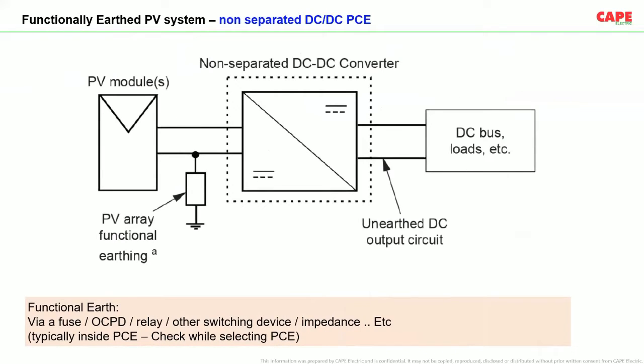This one is a non-separated DC system, but again functionally earthed. The purpose of the functional earthing is that whenever there is a fault in this particular circuit, the fault current will return back through this functionally earthed wire. And on that wire, there is a measurement mechanism and a disconnection mechanism, provided with the help of maybe a fuse or an OCPD or relay or contactor or whatever it is. There is a mechanism available in this route. As a result, whenever the current is more than a certain limit, the functional earthing is disconnected.